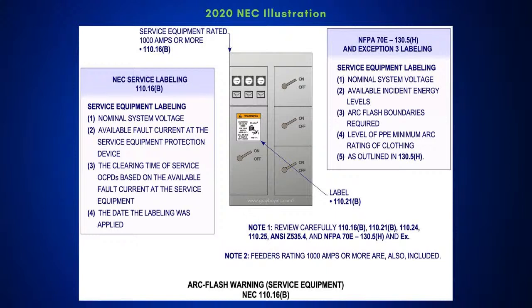If I'm ever doing the table method or the calculation method, I've always said you've got to know three certain things. You've got to know the available fault current, the clearing time, and the working distance. Okay. Well, what they were having problems with was getting the available fault current. So in order to do that, we came in and added what? 110.24, which is your available fault current. And that is required now before you pass the final inspection.